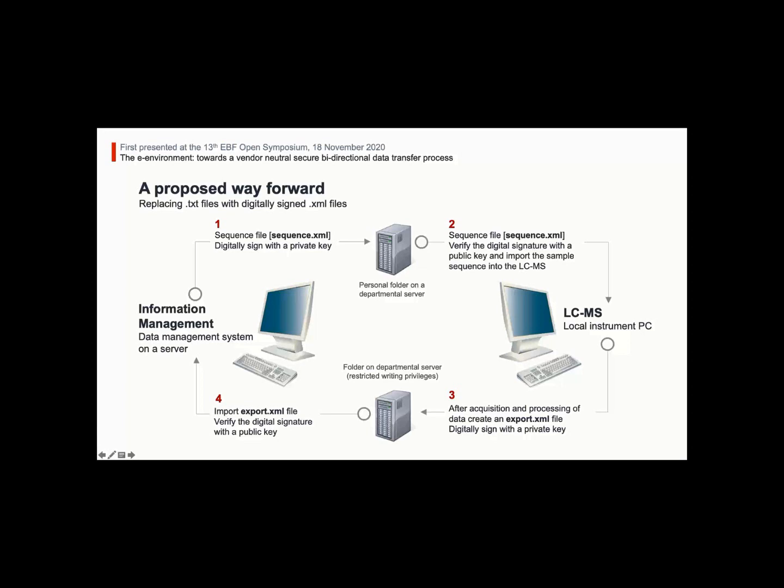And we used the AnIML format in order to do that, so that the LIMS system can create a sequence file in AnIML format and use the digital signature capability of AnIML to secure the content, so that the sequence can clearly be attributed to the LIMS and cannot be manipulated without it being detected. And then the instrument software can suck that in, do what is necessary, and then you have the round trip with an AnIML document that now adds the result information to the sequence information that was already in it, digitally signs that as well, and hands that back to the LIMS.